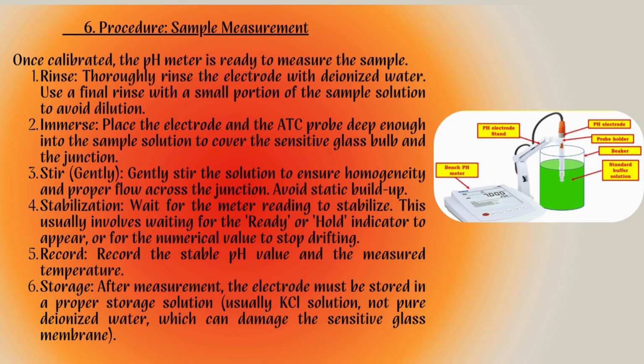Finally, and critically important for electrode lifespan, the storage. The electrode should never be stored in pure deionized water, as this damages the membrane. It must be stored in a specialized storage solution, typically a potassium chloride solution.